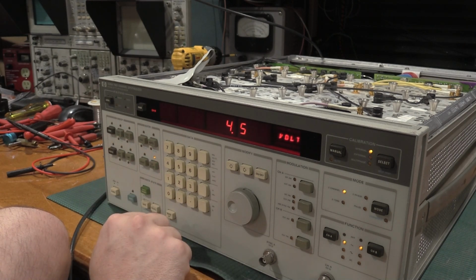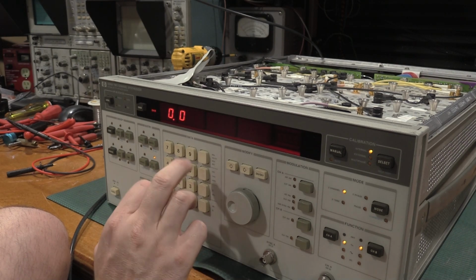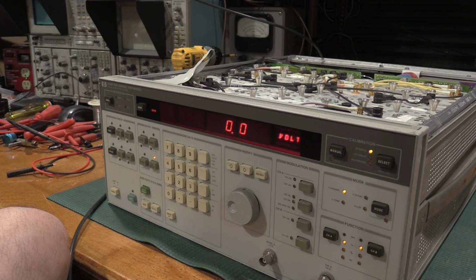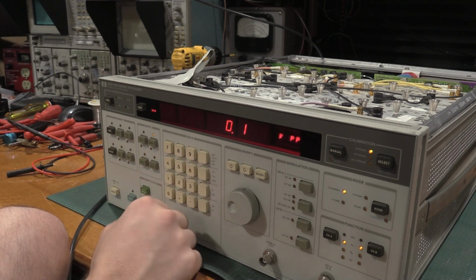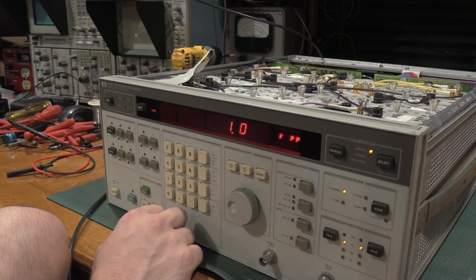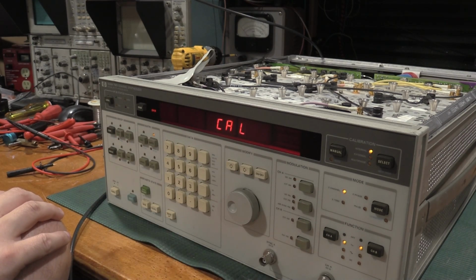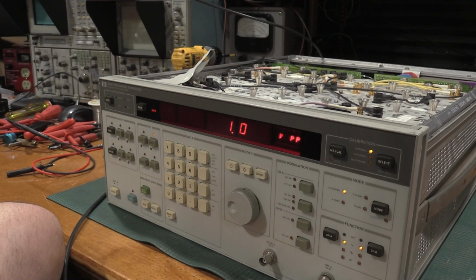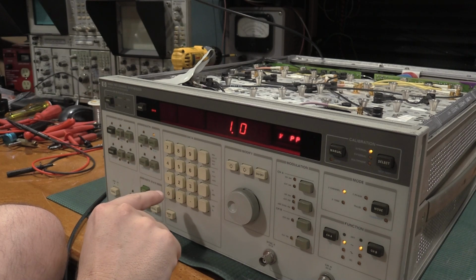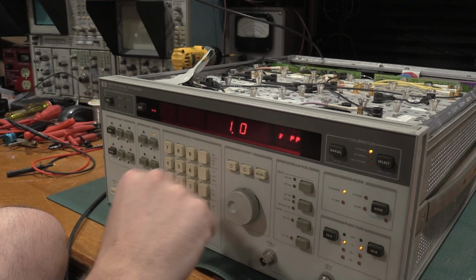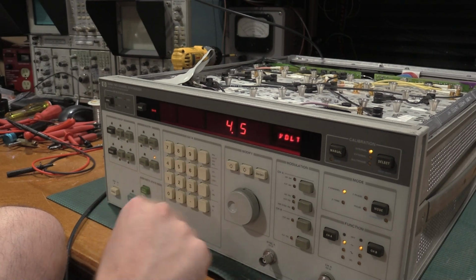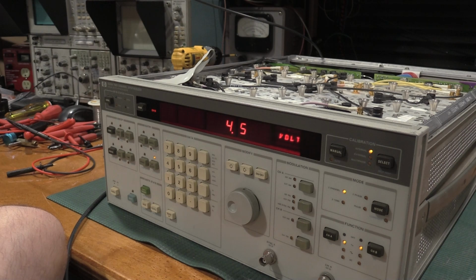Because if I bring the DC offset on channel B down, it's going to fail - it's not, it's going to make a liar out of me. Now it will. Okay, so it's the low range. 1 volt on channel B, 0 DC offset, and then it errors out again. So channel B is definitely the problem, because if I take this back to 1 volt with 4.5 volts of DC offset, it's going to go just fine. Yeah, it doesn't care. So I have another relay with bad contact resistance, and we will need to find that.